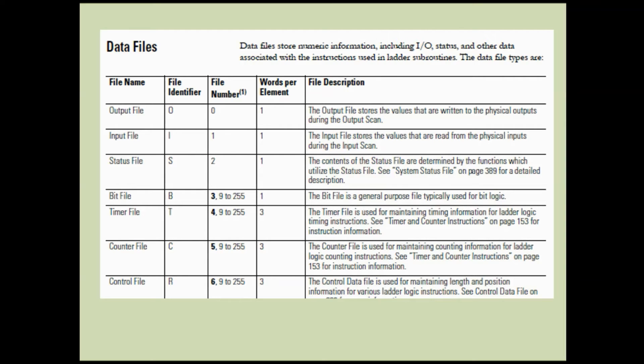Here's an example of the data files taken from the user manual for the MicroLogix 1500. For an output file the identifier is O, for an input file it's I, for a status file it's S. An example of a status file is the first pass bit - these are pre-stored status information that the PLC has, which we can use or look at when troubleshooting. Bit files start at B3, timer files are T4, counter files are always C5, and control files follow the same pattern.